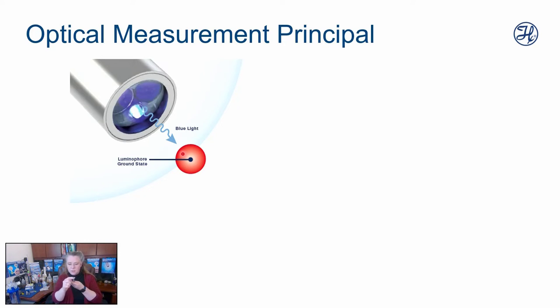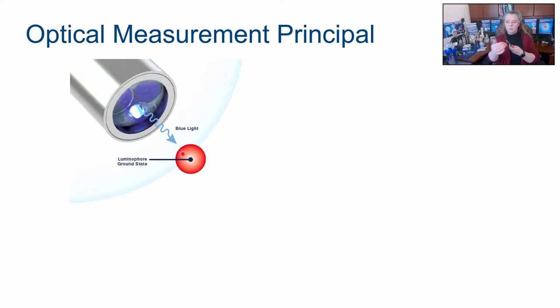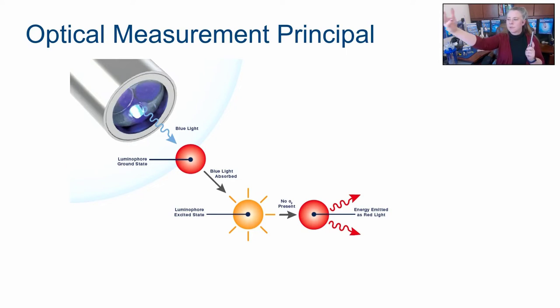The silicone that you see on the end here's only job in the entire world is to block external light from going inside the probe. So the only light measured inside is the light generated inside. So the light comes out, it goes in, it hits the back of the luminophore. And if there's no oxygen present, the luminophore gets all excited and bounces around. And with no oxygen present, it emits a red light out. Okay, blue light, red light.